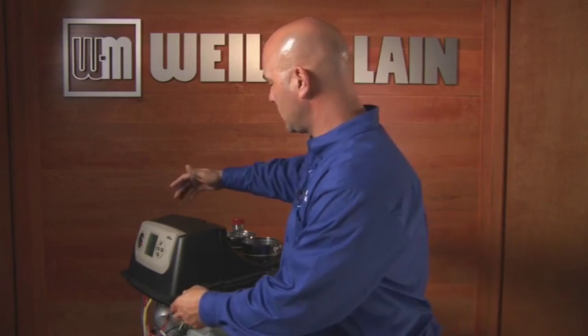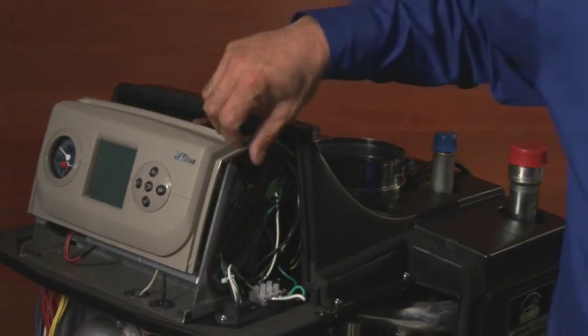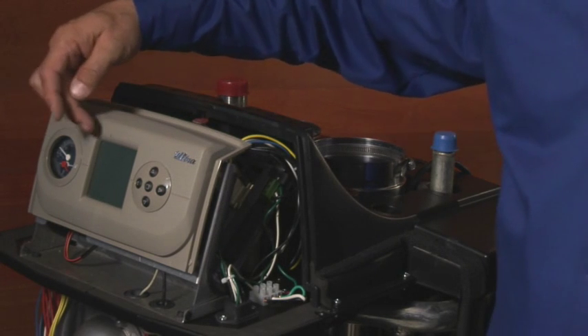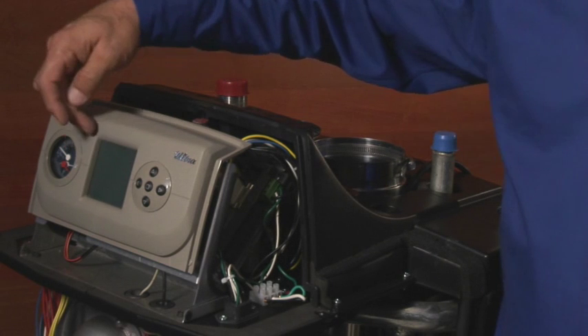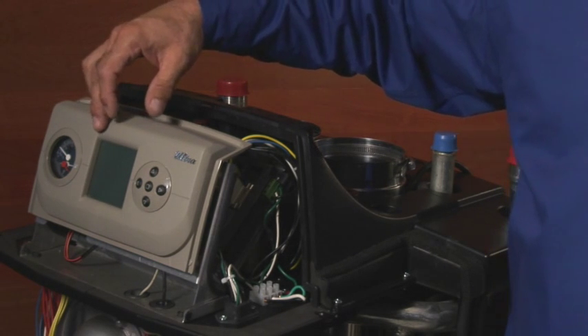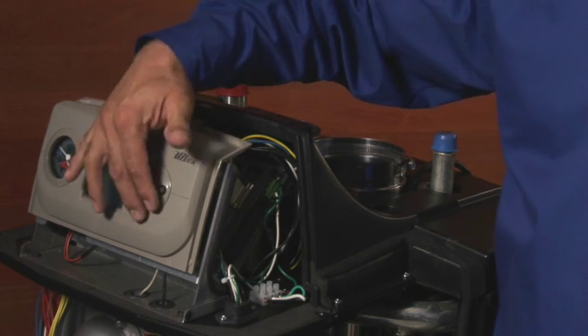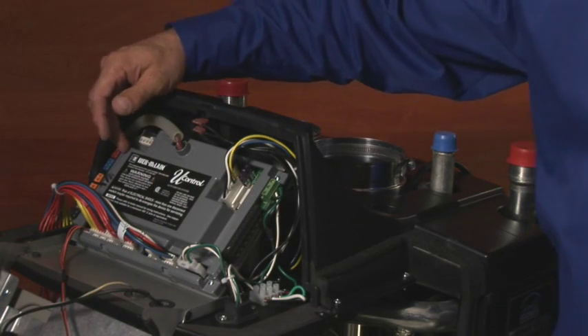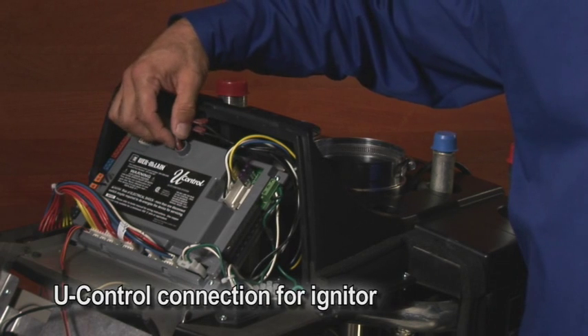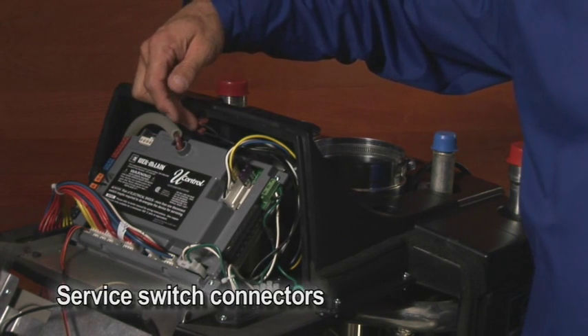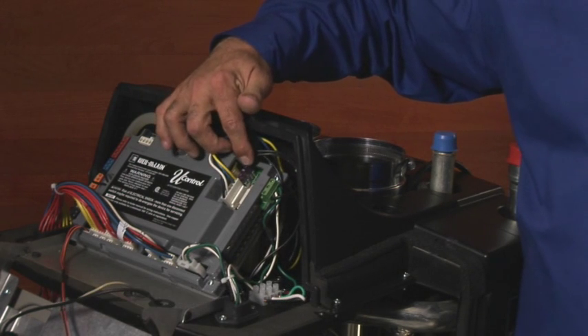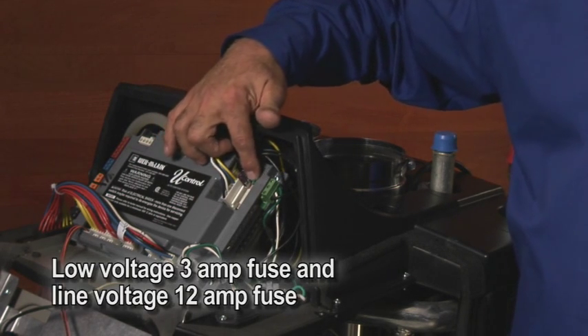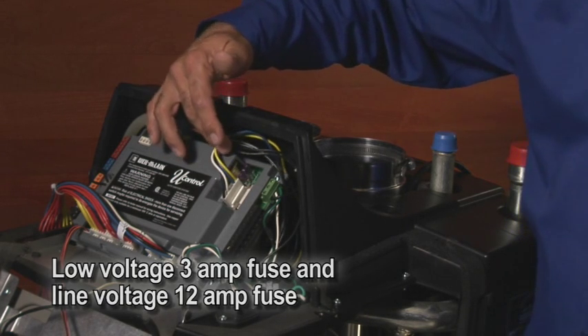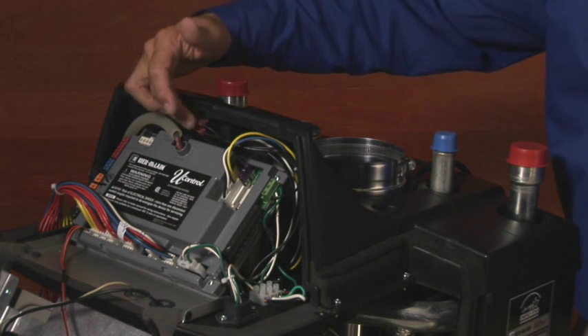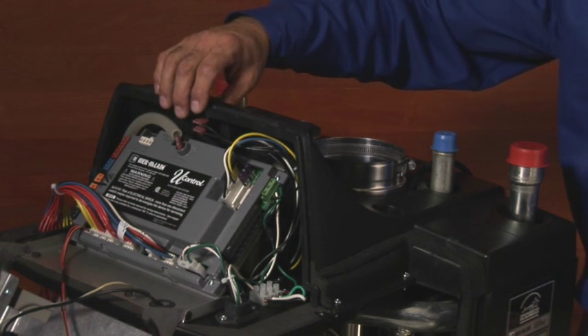Okay, up top here on the Ultra, we're going to remove the control pod. And here's the display. The display has the temperature and pressure gauge. Your window here, 3.5-inch LCD screen, and it'll give you all the information that the boiler will display. You know your push-button keypad: up, down, left, right, and enter. This will swing down. Under here we have the U-control. The U-control has the connection for the igniter. Here's your switch, backside of your on-off switch. Over here we have a low voltage fuse protection and line voltage fuse protection on the U-control that's built into all the controls. Just behind the backside of the switch, your on-off switch is right here.